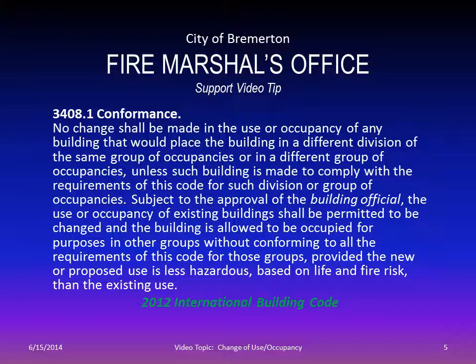Here's the code language that defines this. 3408.1, and this is conformance out of the building code. No change shall be made in the use or occupancy of any building that would place the building in a different division of the same group of occupancies or in a different group of occupancies unless such building is made to comply with the requirements of this code for such division or group of occupancies. Subject to the approval of the building official, the use or occupancy of an existing building shall be permitted to be changed and the building allowed to be occupied for purposes other than in other groups without conforming to all the requirements of this code for those groups, provided the new or proposed use is less hazardous based on life and fire risk than the existing use. And that's kind of the whole part. Occupancy and use, and then life or fire risk.